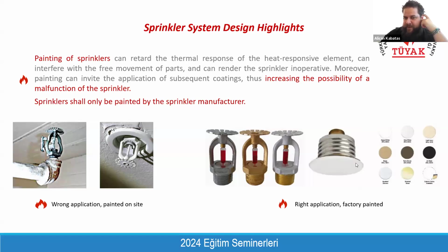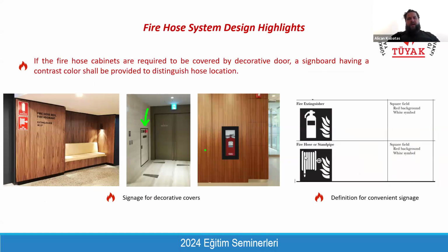And concealed type sprinkler systems have some plates. These plates are also not allowed to be painted, but you can buy them with a RAL code which matches your ceiling design. But all of this coordination, the code selection, the color selection, and the procurement should be coordinated by the architect, and all of the required information, for example, the color code of your ceiling and the preferred type of sprinkler heads, either semi-recessed or concealed, should be defined and determined by the architect. That's why you need to inform the mechanical designer accordingly. And as you know, we have fire hoses within the floors, and these hoses are not liked by architects.